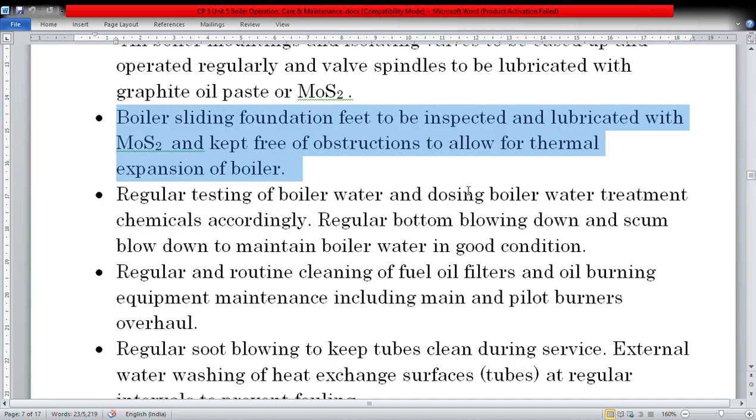Any floating object, maybe a little particle of oil, even if we can see it, or any floating object which is not desired; I gave oil as an example because oil will float above the water. Those things are removed by scum blow down. So we have valves provided for the bottom blow down, and on top we have the scum blow down valves. Two may be on the overboard side, that is the ship side, and two on the boiler side.